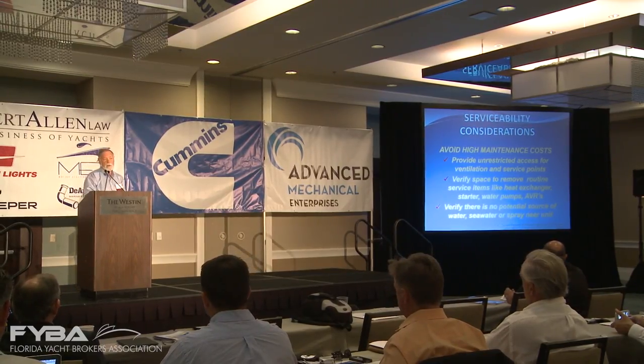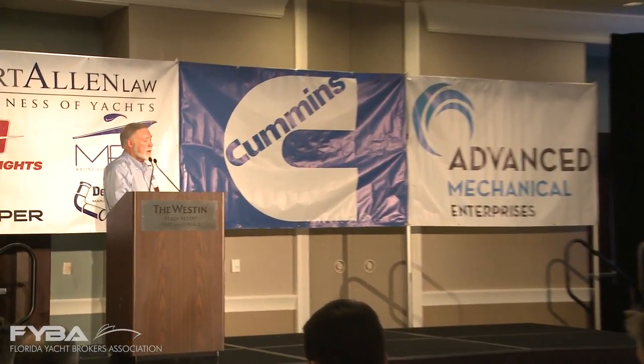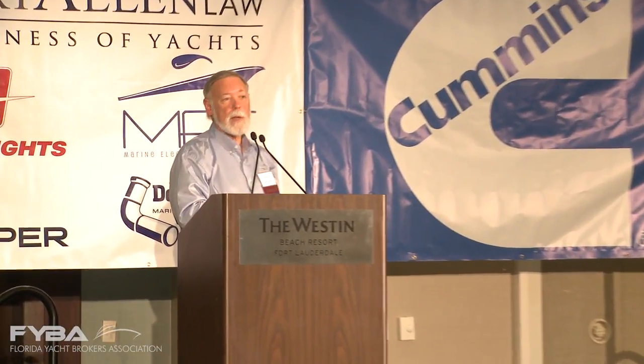We had a problem with a major yacht builder that buys lots of Northern Lights generators. They built several 50-meter yachts with paired 99 kW generators, and all of a sudden our auxiliary electric cooling fans on those sound enclosures started falling off, melting and falling off. It turned out they'd only allowed about 1.5 inches of clearance between the backside of the generator and the bulkhead, and that happens to be where the ventilation slots are. All the ventilation occurs on the backside, so you have to make sure you haven't obstructed it. It's nice to make room in the engine room, but you still have to have ventilation.